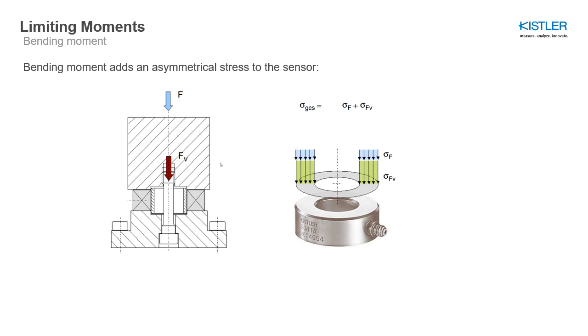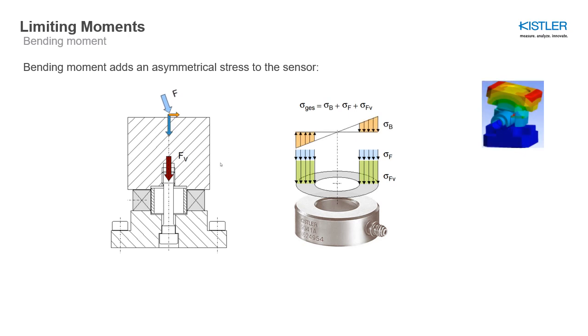On the right hand side you can see the stress that is distributed along the surface of the sensor, which adds up from the preload force and the process force together. Now, if you're not absolutely in line here with your force in the x-axis going through the center of the sensor, you apply a bending moment. You have a shear force here on the top, which generates an asymmetrical stress to the sensor that you can see here on this side. So the distribution of the force along the surface of the sensor is not given anymore, because on the left-hand side you relieve the sensor, and on the other side, with the same amount of stress, you additionally add some stress to the surface of the sensor.